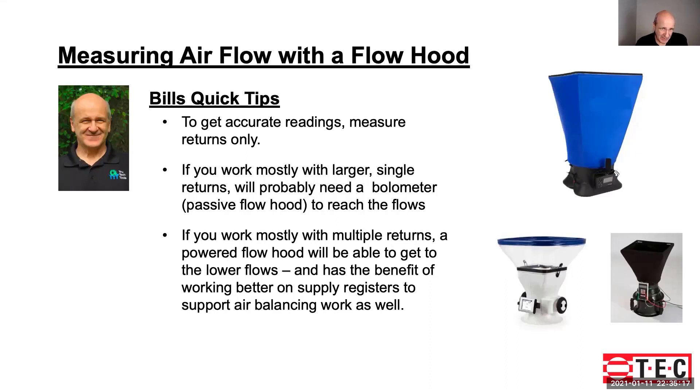Today I'm going to give you a couple of quick tips on measuring airflow with a flow hood. To get accurate readings, you want to measure returns only — this is for residential applications mainly. If you work mostly with larger single returns, you'll probably need a balometer or a passive flow hood to reach the correct flow levels for your application. If you're working mostly with multiple returns, a powered flow hood is great — probably one of the better ways to do it because you're going to have lower flows at multiple returns. You also have the benefit of it being more accommodating for supply registers in different locations, being more compact, and you can use it to support air balancing work on a supply basis too.